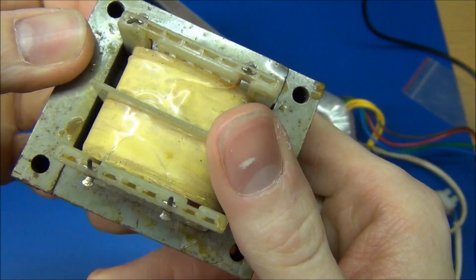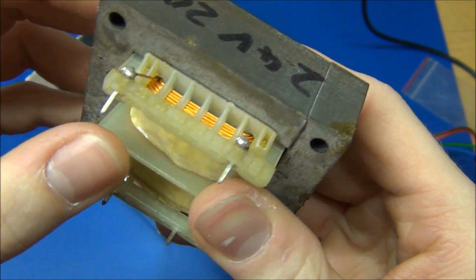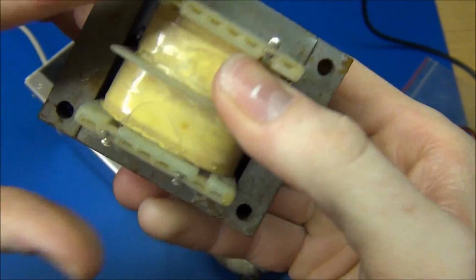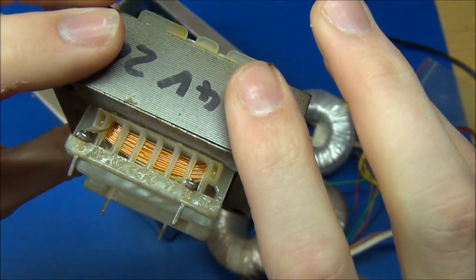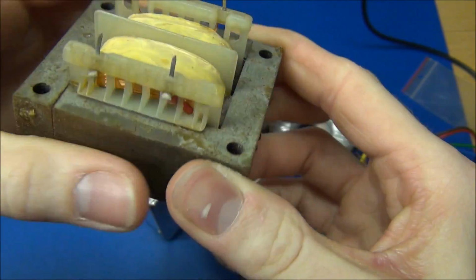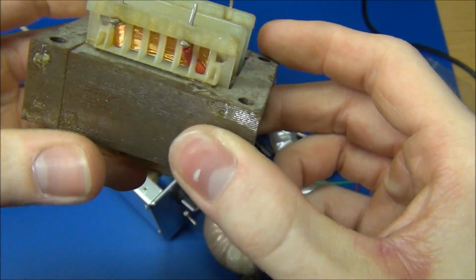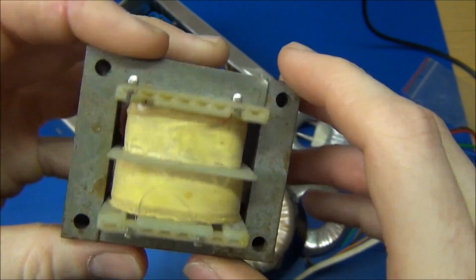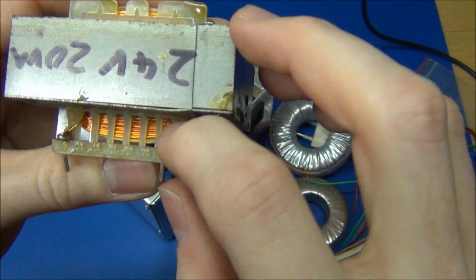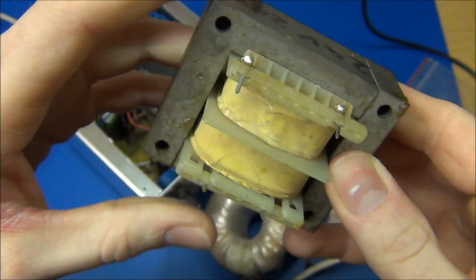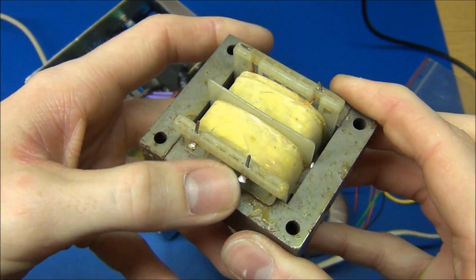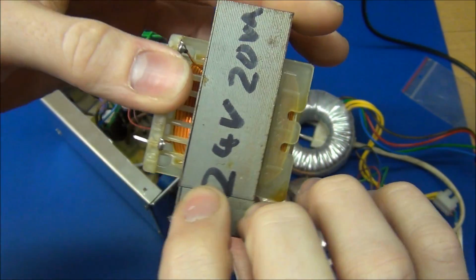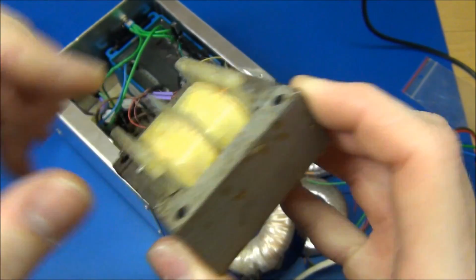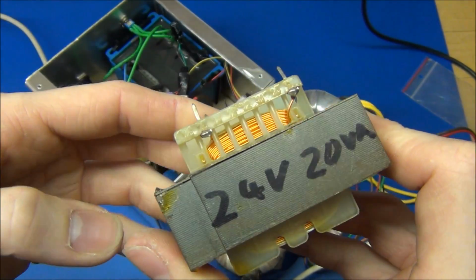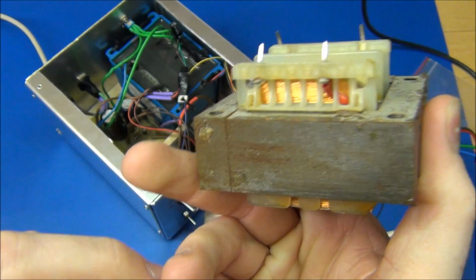This transformer has only one secondary winding and one primary winding. You can tell which is which because since this is a step-down transformer rated for mains voltage, the fine wire on this side is the primary winding, and the coarse wire on this side is the secondary winding, since the voltage drops in the same ratio as the turns. So if this is a 24 volt transformer, with 240 volts going in and 24 volts out, it would be 1/10 of the turns on this side compared to this side.